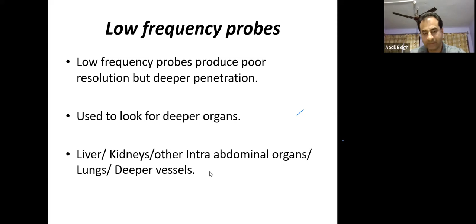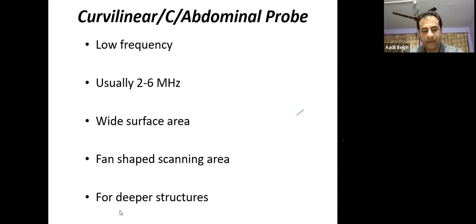Now the types of probes. We have the curvilinear probe, commonly known as the abdominal probe. It has low frequency, 2 to 6 megahertz, that is 2 to 6 million cycles per second. It has a wide surface area; it's a bigger probe, so the examination area is more. It has a fan-shaped scanning area and produces a fan-like image, and it is for deeper structures. So it has good visualization of structures more than 4 centimeters away from the probe. Less than 4 centimeters from the probe, it has poor visualization.